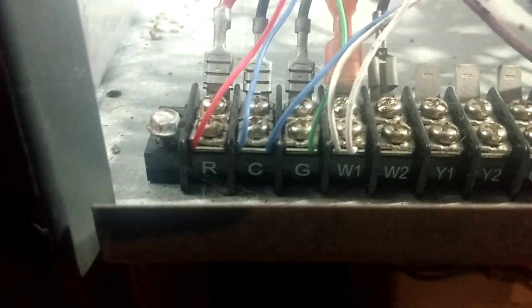So then we want to come over here to our low voltage strip and verify our low voltage. We're just going to go common to R, and we've got 26 there. And now we're just going to jump over here and go common to G. And if you can see that, well, I'm on there. You'll have to trust me. There's common to G. And we do have 26 volts, because right now I have the thermostat set to off with the fan on. And of course, we have no blower. Our power's here. Our low voltage is here.